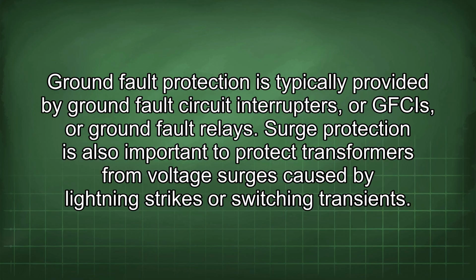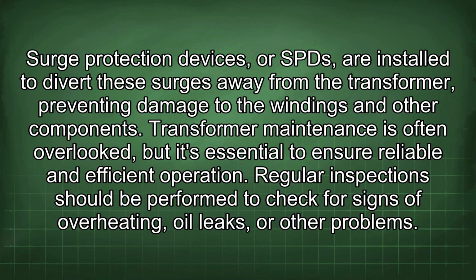Surge protection is also important to protect transformers from voltage surges caused by lightning strikes or switching transients. Surge protection devices, or SPDs, are installed to divert these surges away from the transformer, preventing damage to the windings and other components. Transformer maintenance is often overlooked, but it's essential to ensure reliable and efficient operation.